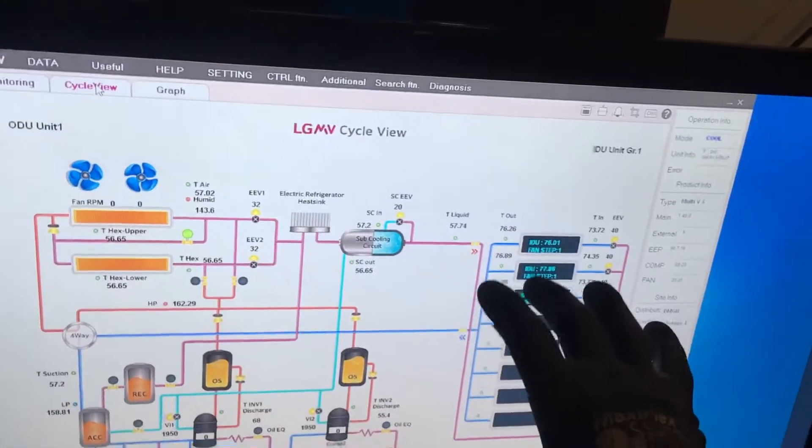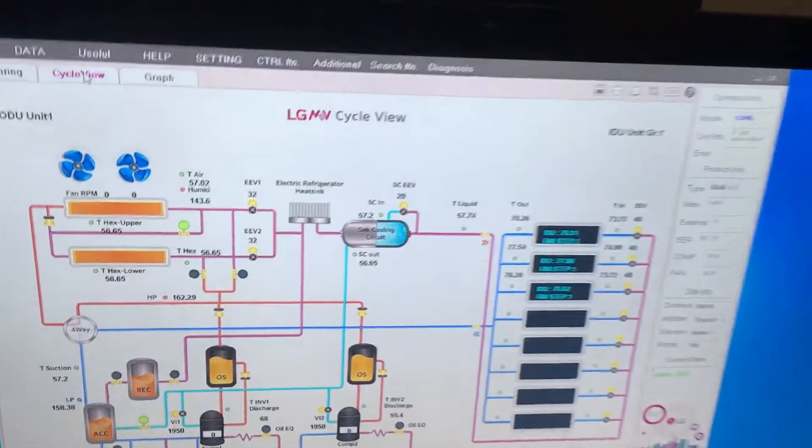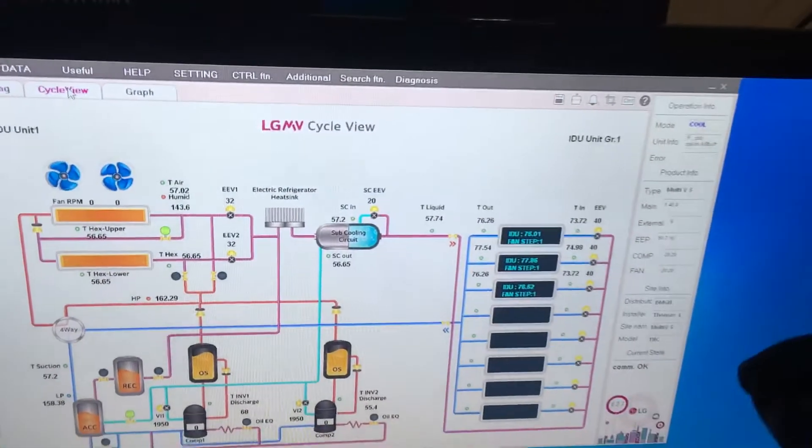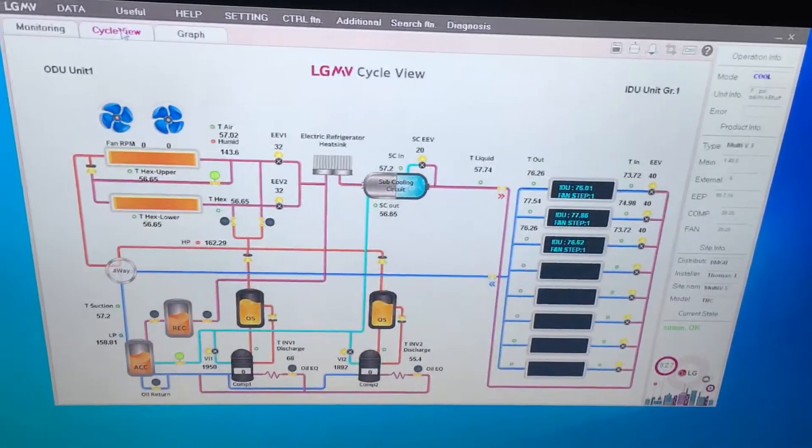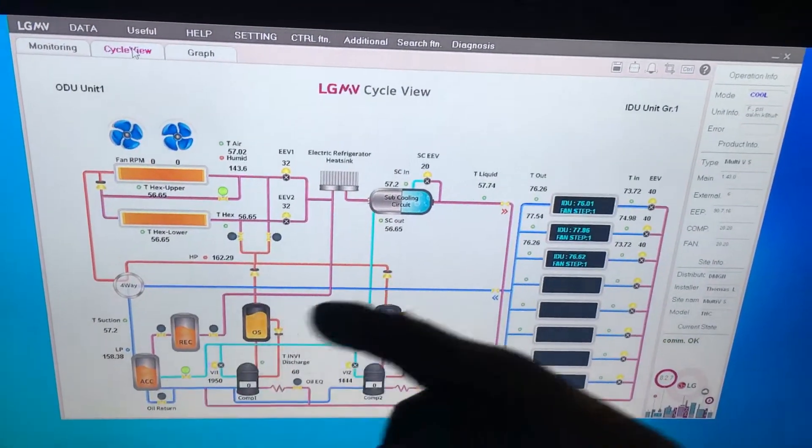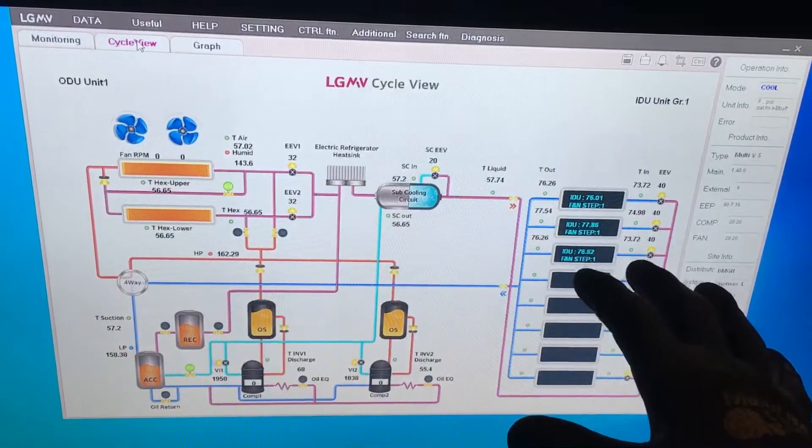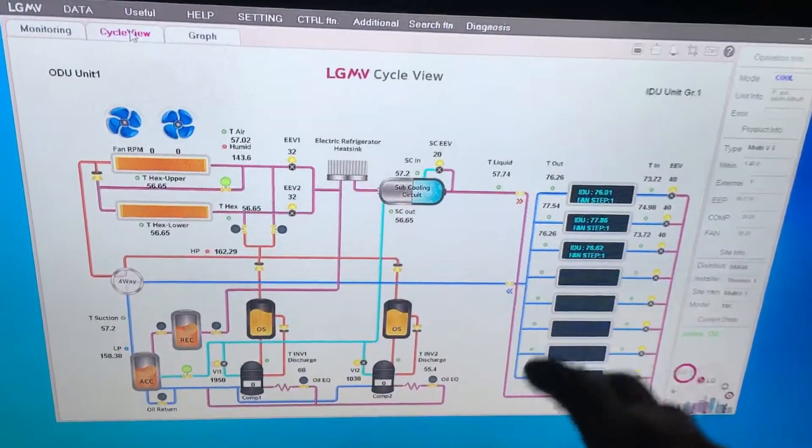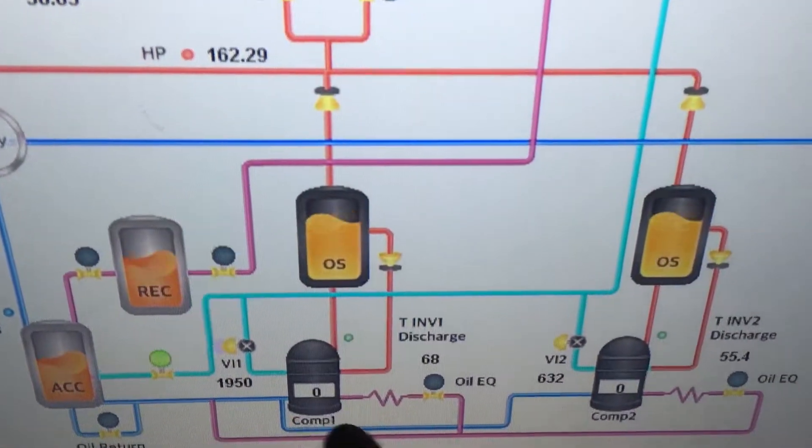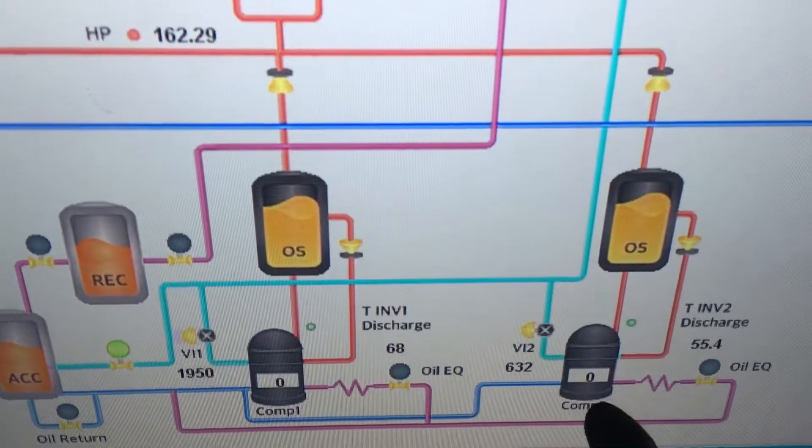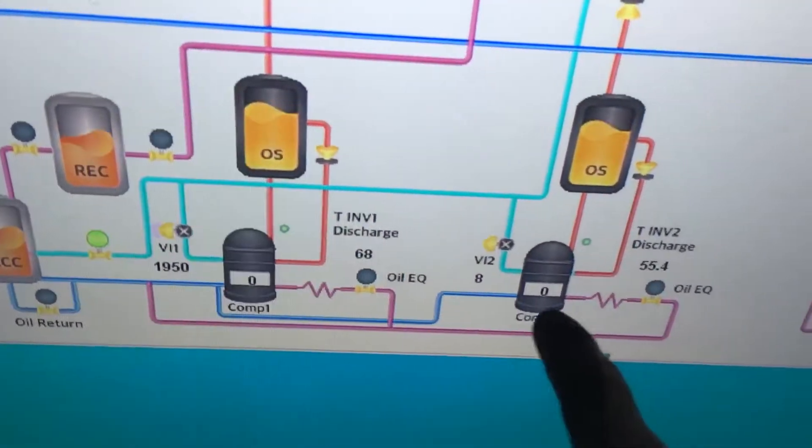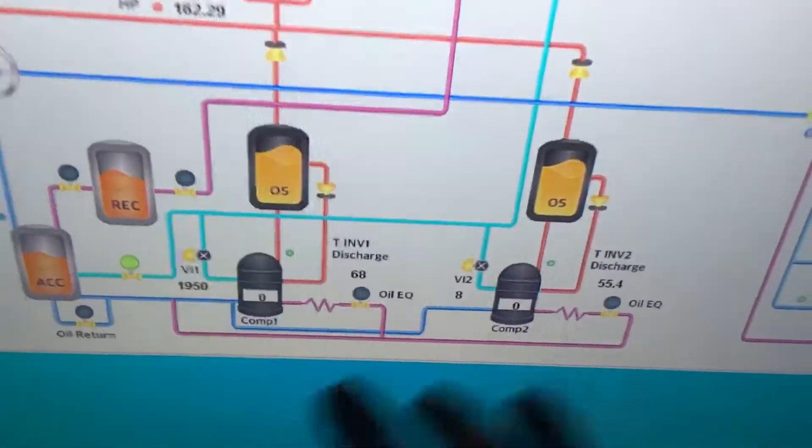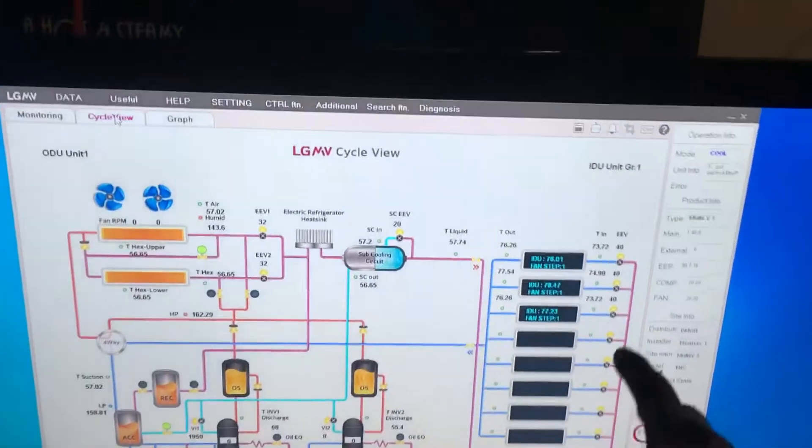So now what we're performing is a failsafe. We're killing the other system. This one is on, like if it was in backup mode. And as you can see down here, it says zero zero at the compressors, so the compressors are not engaged at all. If you could see the mirror identical, if we had it hooked up over at the other screen over there, you would see the other three air handlers.